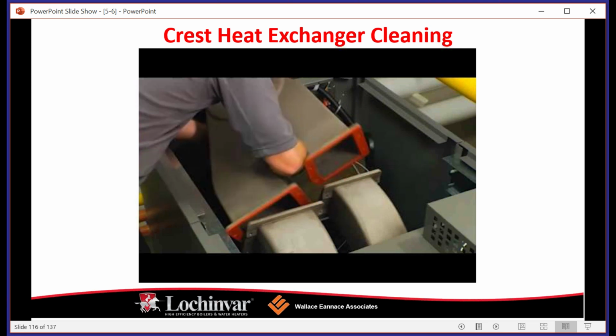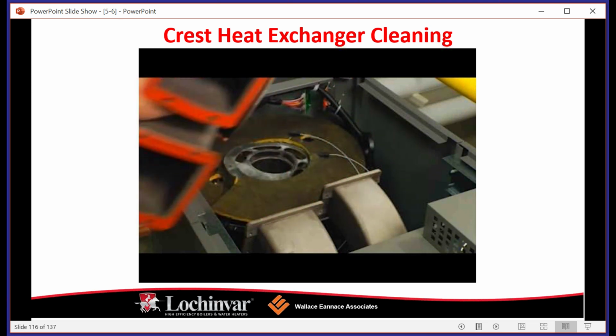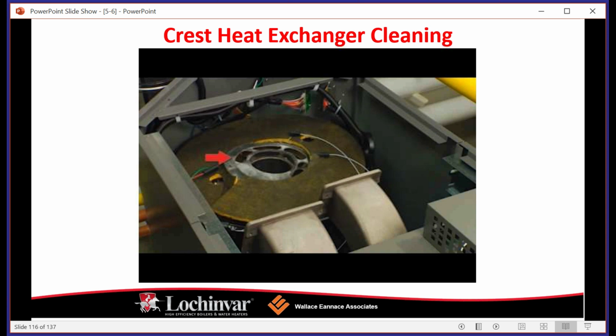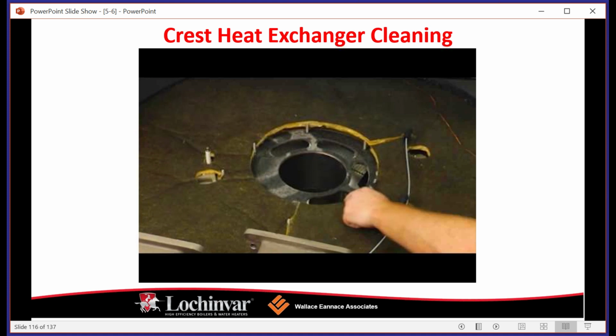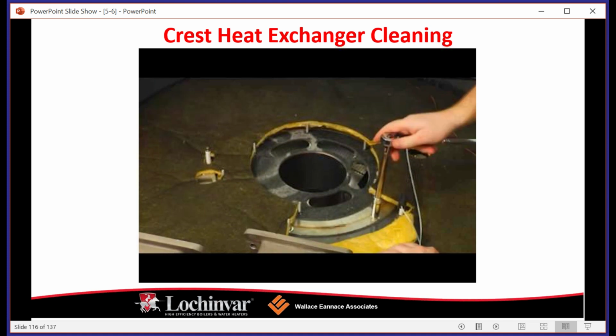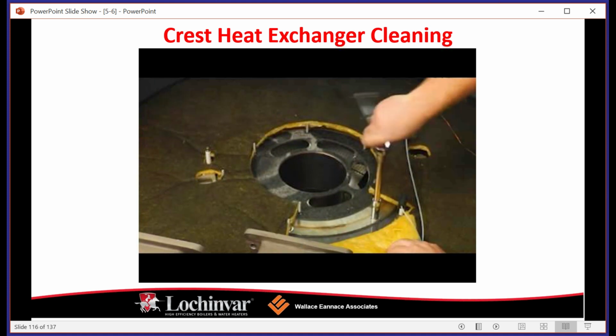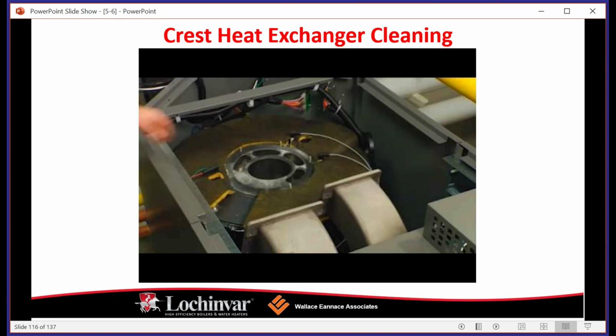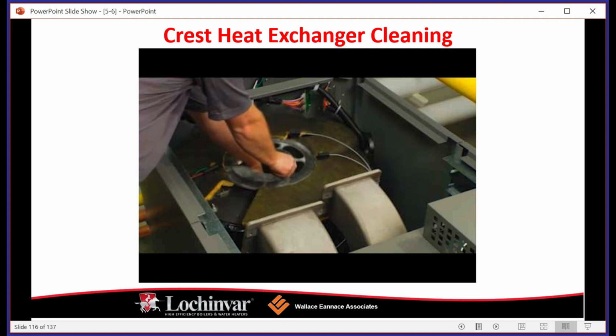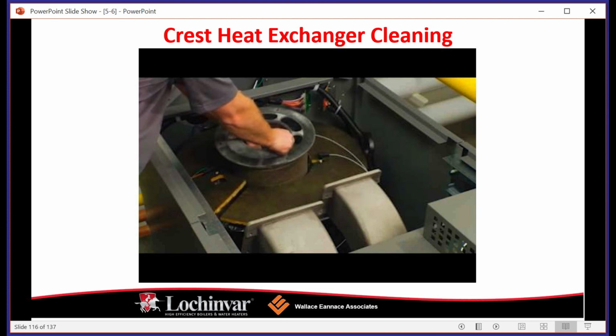Okay, so again, cleaning the heat exchanger, cleaning the blower, and removing and cleaning the burner. Generally speaking, if the boiler is installed correctly and you don't have animals living in your fresh air intake, or smoke or dander, or like those guys or girls that we saw having lint pulling in right next to the fresh air intake, it really shouldn't be something that you need to do often.